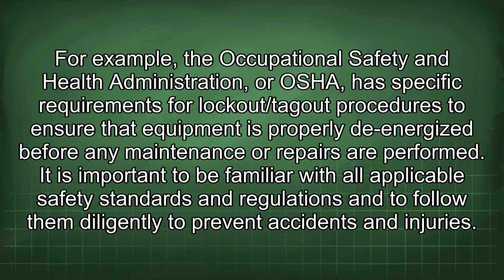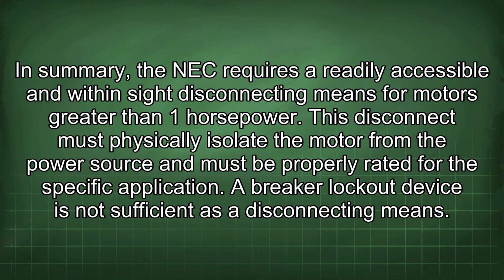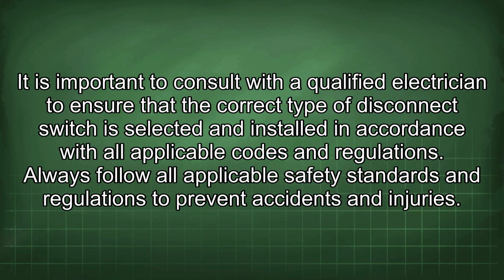accidents and injuries. In summary, the NEC requires a readily accessible and within-sight disconnecting means for motors greater than 1 horsepower. This disconnect must physically isolate the motor from the power source and must be properly rated for the specific application. A breaker lockout device is not sufficient as a disconnecting means. It is important to consult with a qualified electrician to ensure that the correct type of disconnect switch is selected and installed in accordance with all applicable codes and regulations. Always follow all applicable safety standards and regulations to prevent accidents and injuries.